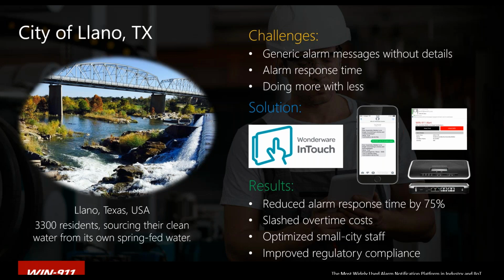They're utilizing our SMS text messaging, email, and voice calls over analog phone lines, using a VoIP to analog converter to make that happen. Once we got installed, we tied directly into their InTouch alarm database. They select the alarms we need to notify on, monitoring equipment like electrical power, tank levels, flow rates, pressure, and chemical feed rates. They're able to now push out the details within a matter of seconds, getting all the details necessary to make decisions to get the proper personnel over there to fix the problem and know where it's located.